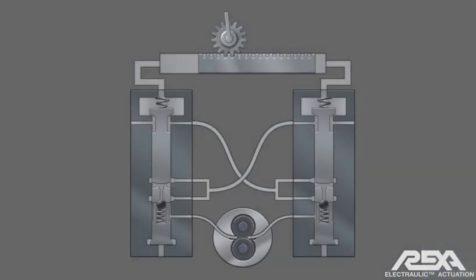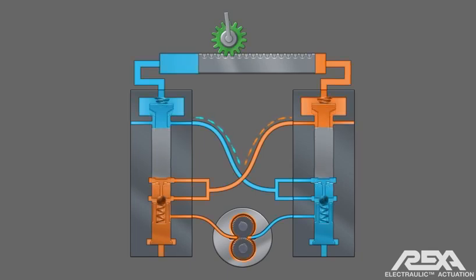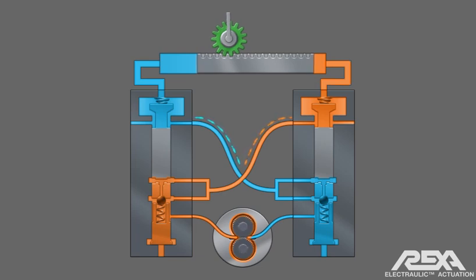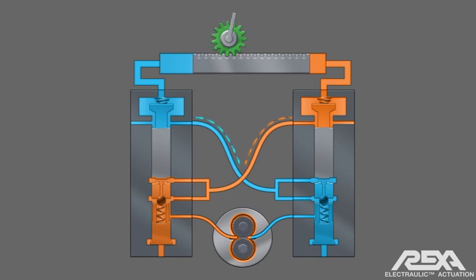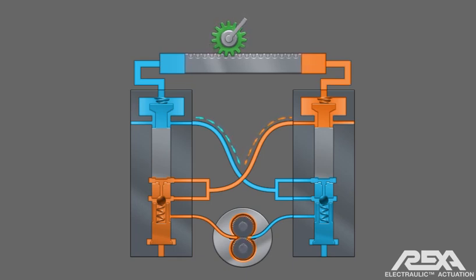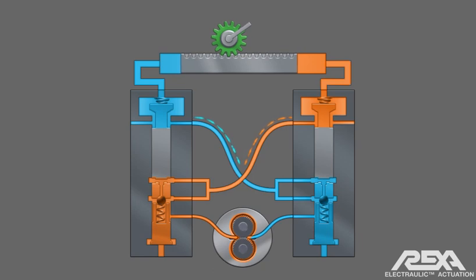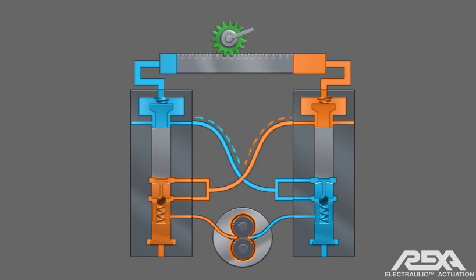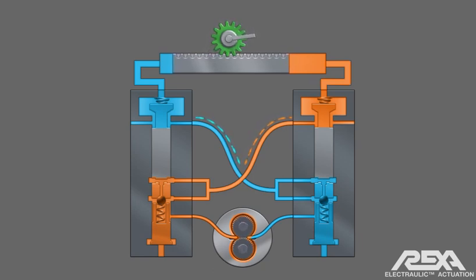The flow match valves are a unique pilot check valve flow control type design. The design allows for a constant oil volume to be moved back and forth from one side of a double acting cylinder to the other. This happens in a smooth and stable manner regardless of the applied load or any load variations, including bi-directional dynamic loads from zero load to full actuator output.